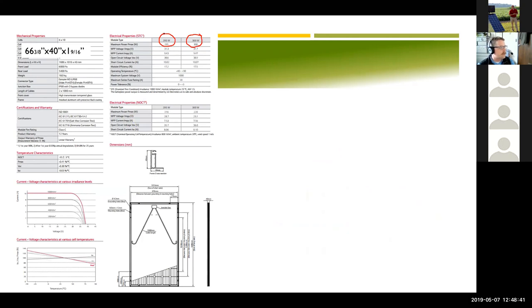But pretty much all solar panels have a very standard size. Sometimes their depth, how thick they are, is a little different because of their rim or the frame that they're in, but they're about 5.5 feet by just over 3 feet. So in this case they're 66 by 40 inches, by about 1 9/16. So they're all physically the same size. And that actually is something that's very positive about the solar industry today: if I broke a solar panel and had to replace it and couldn't get the exact same one, I can just buy one that is similar and has the same physical dimensions and it fits right in, doesn't really even look odd. So I've replaced them with different brands and I can hardly tell that I did it on some solar arrays. One got hit by a rock one time from a shredder and broke.